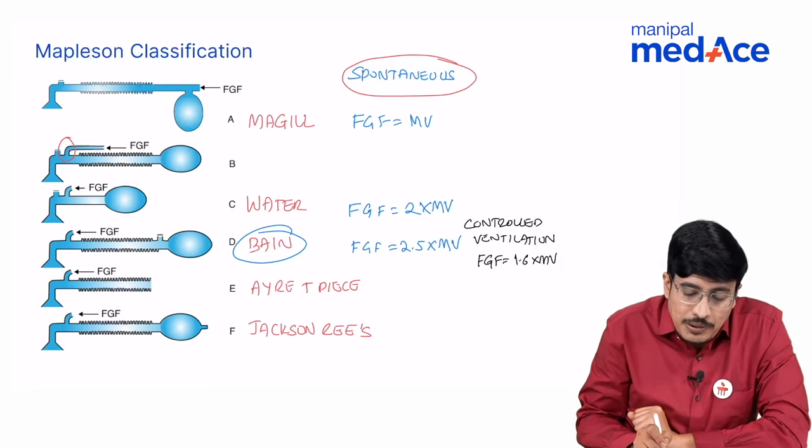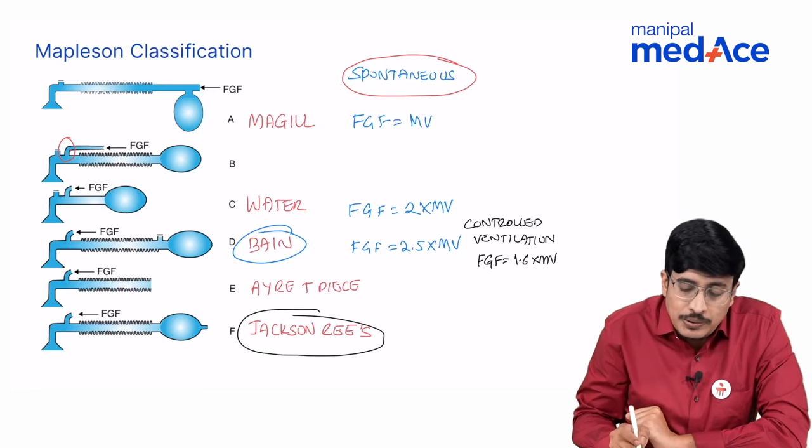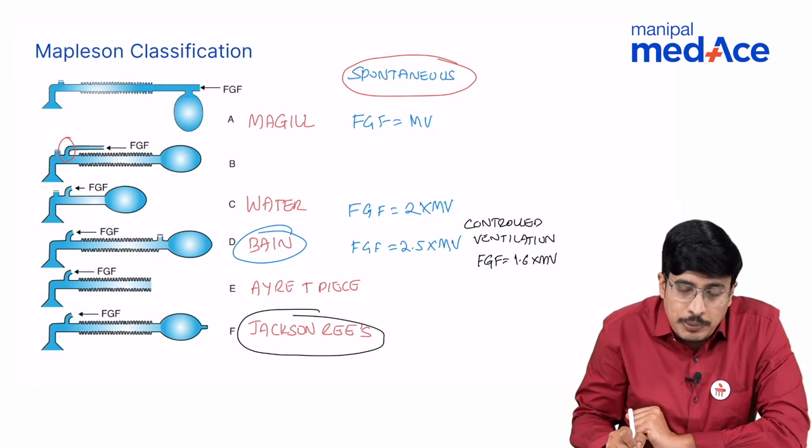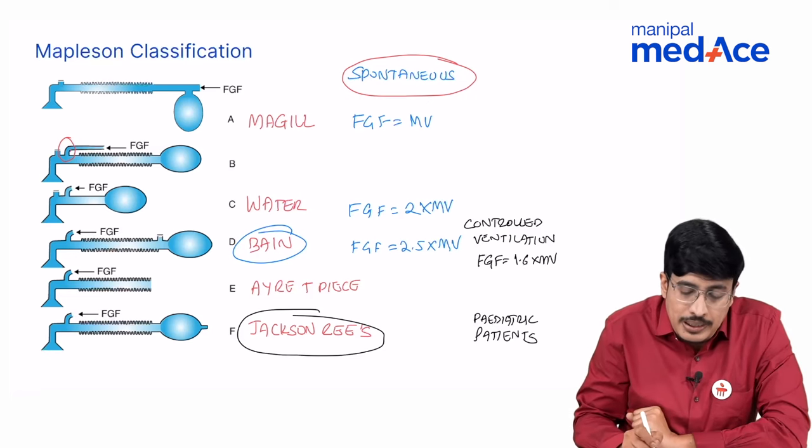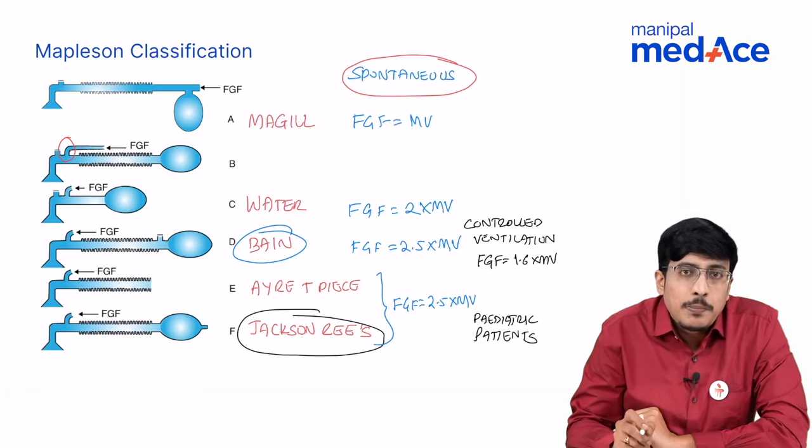Whereas the circuit that we commonly use is Jackson-Rees circuit. It is a circuit of choice in case of pediatric patients. Both in type E and F, the fresh gas flow is again 2.5 times the minute volume similar to Bain circuit.